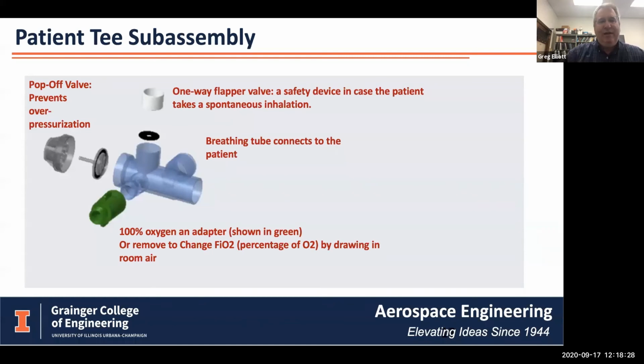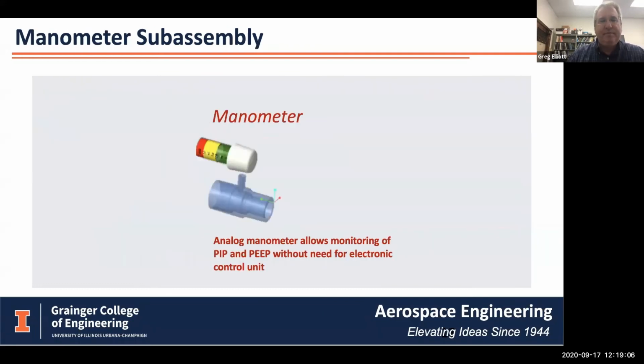Then we have an oxygen adapter that is basically an ejector that can take 50 PSI of oxygen in, and then set the flow rate, or the pressure into the device. By removing that, you can change the FiO2, which is the percentage of oxygen. So the green device, when you install it, gives 100% oxygen. When you remove it, you're getting about 50% room air through the device. Then we have the manometer, which is just an analog, spring-loaded pressure gauge, so that you could monitor that the device was working properly and monitor the PEEP and PIP pressures.